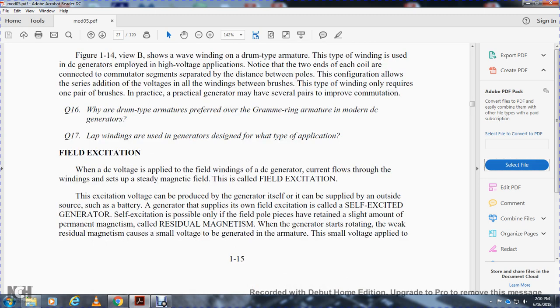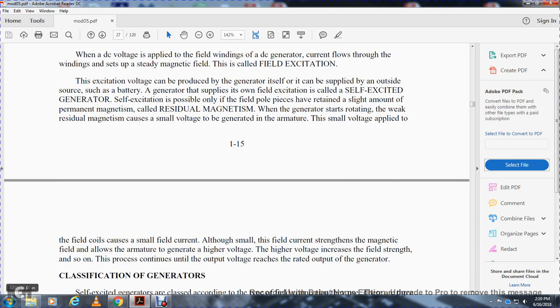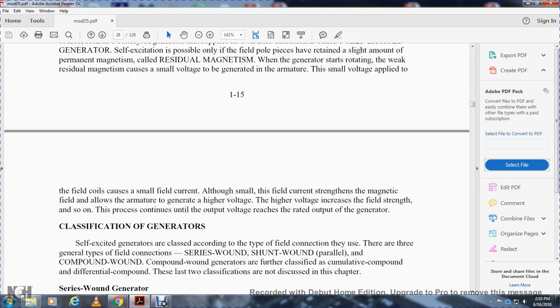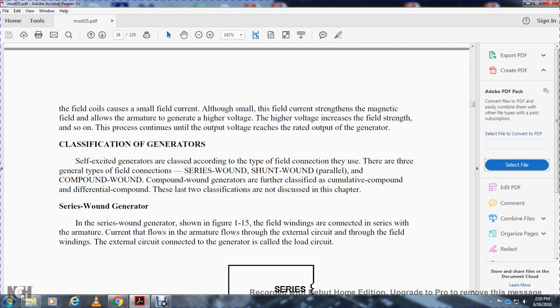Field excitation: when DC voltage is applied to the field windings of a DC generator, current flows through the windings and sets up a steady magnetic field — this is called field excitation. The excitation voltage can be supplied by the generator itself or from an outside source such as a battery. A generator that supplies its own field excitation is called self-excited. Self-excitation is possible only if the field pole pieces have retained a slight amount of permanent magnetism called residual magnetism. The generator starts rotating, and the weak residual magnetism causes a small voltage to be generated in the armature. This small voltage applied to the field coils causes a small field current, which strengthens the magnetic field, allowing the armature to generate higher voltage, which further increases field strength, and so on, until the output voltage reaches the rated output. The self-excited generators are classified by the type of field connection used — three general types: series-wound, shunt-wound (parallel), and compound-wound. Compound-wound generators are further classified as cumulative compound and differential compound, which are not discussed in this chapter.